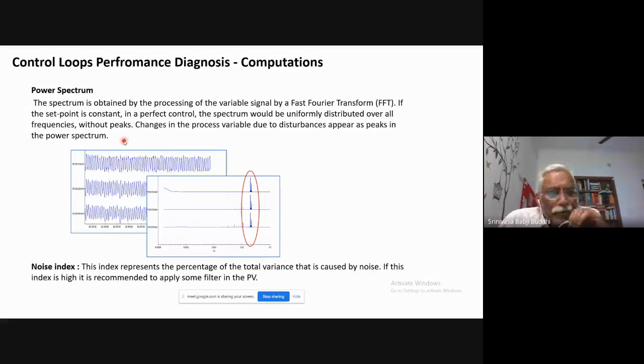If there are no large variations, no major oscillations or disturbances in the process, the power spectrum will be steady, with very small variations remaining constant throughout. Suppose there are a lot of disturbances or large variations, they appear as a spike at that particular frequency in the power spectrum. This way, it is very easy for us to identify at what frequency these oscillations are taking place, and at that particular frequency, we also get the corresponding amplitude from this Fourier transform.